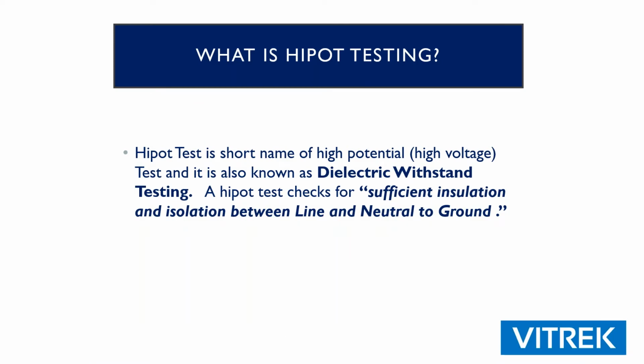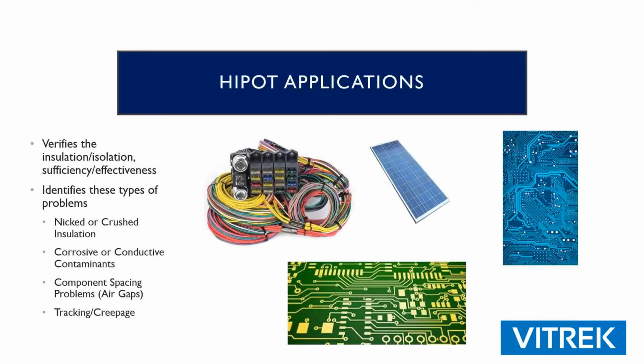All right, so what is HIPOT testing? It is short for high potential. That's where we get the contraction HIPOT. It's a dielectric withstand test. Basically what we're doing is we're confirming that there's enough insulation between line and neutral for your mains power and chassis or earth. With that test, we can verify that the insulation is sufficient if there is a voltage overshoot or something like that from the grid.